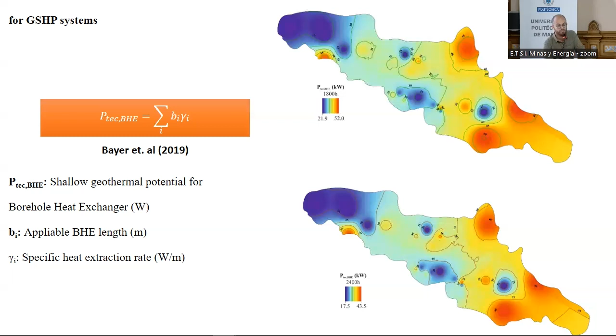I think this is the most important point in my PhD: sustainability of these systems. Ground source heat pump shallow geothermal systems have many advantages, but if used extensively across a planet or area, there could be thermal interference or thermal interactions between systems, causing them to fail. So if you want to apply a shallow geothermal system in your home, you should consult professors or perhaps the municipality to check whether your area is suitable.